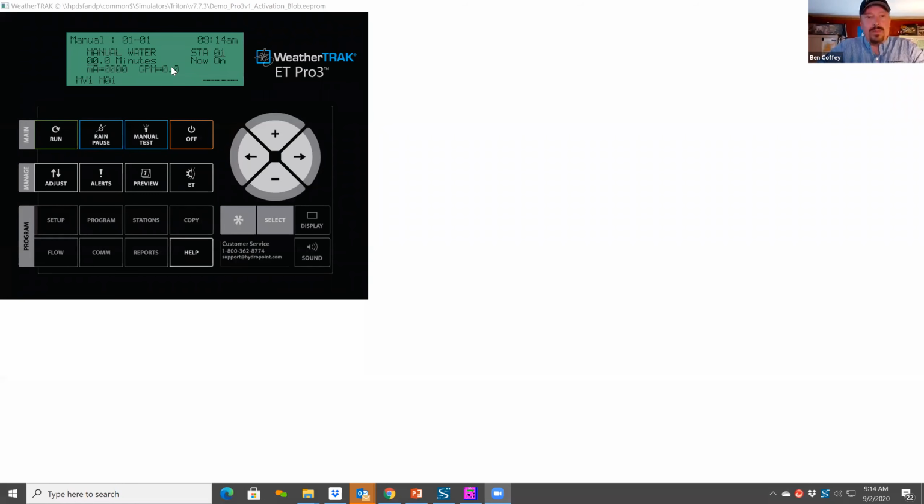So the way that we test is we understand the station we're looking at, we have an approximate calculated value, and we compare that to what we're showing on the screen. You'll also see, to Jonathan's point, during pipe fill, that number gets larger. So you'll see it climb, and then come back down and balance out. The balanced out number is what you're waiting for, because that's what really shows what you're using at that point.